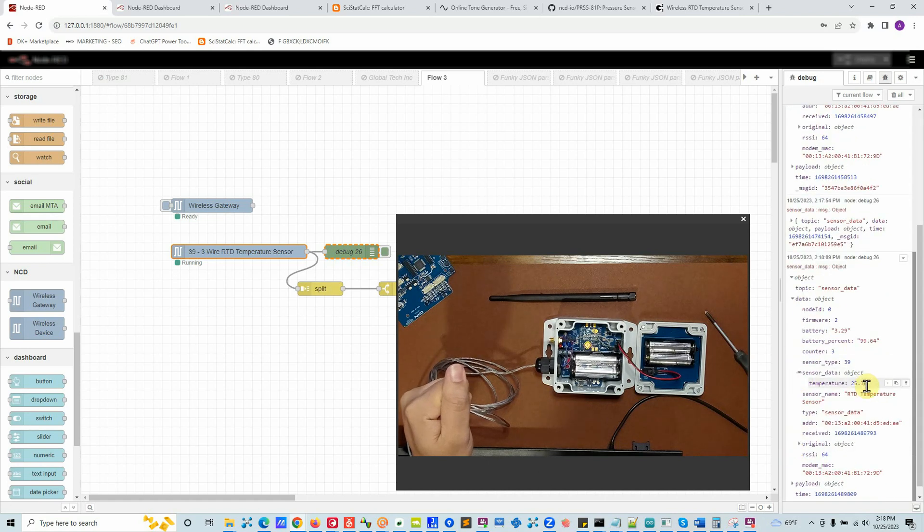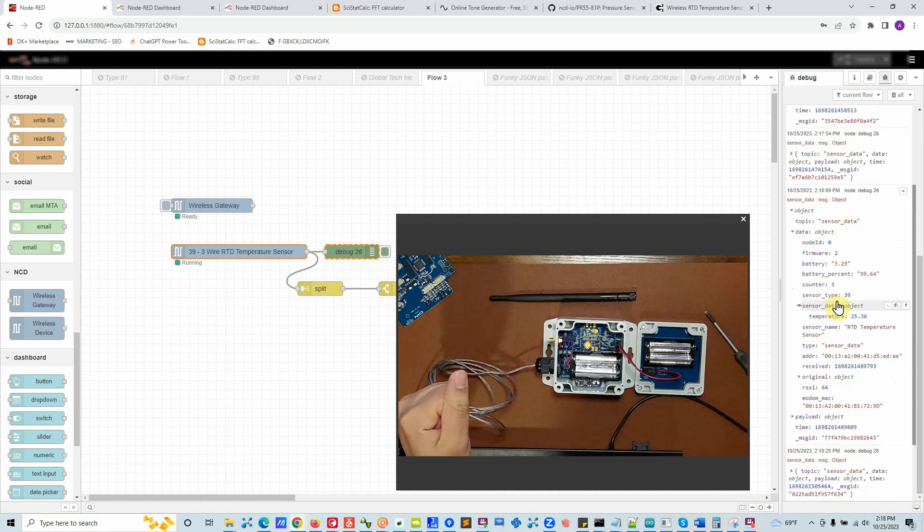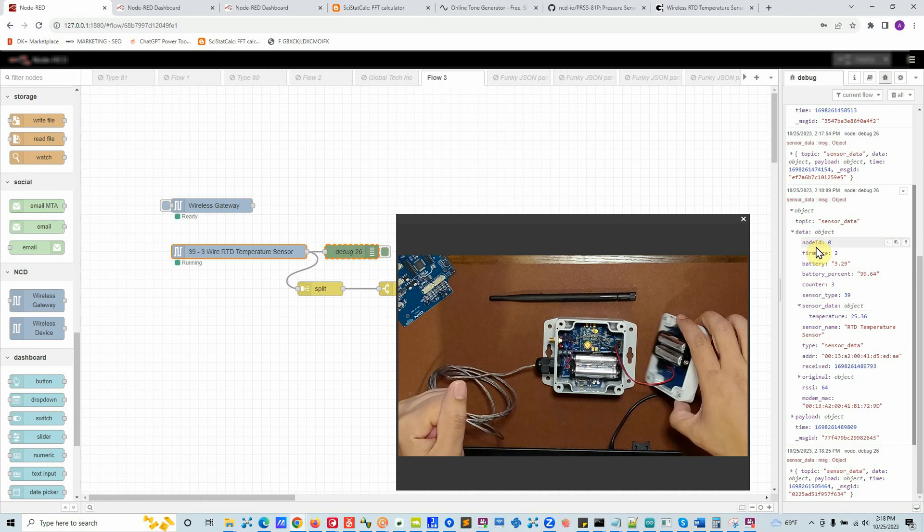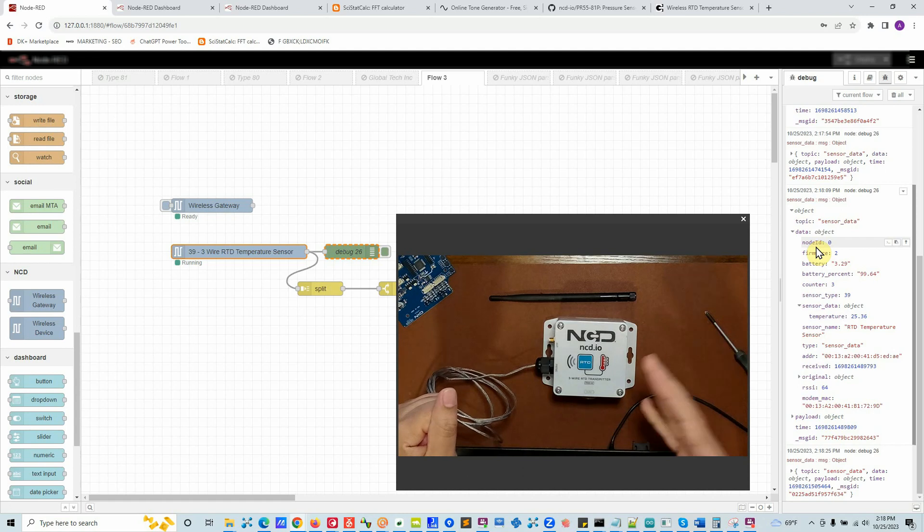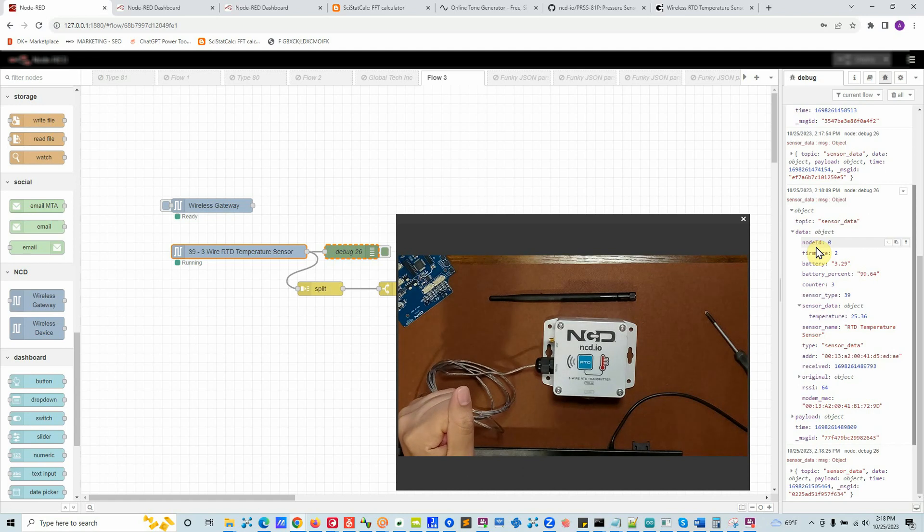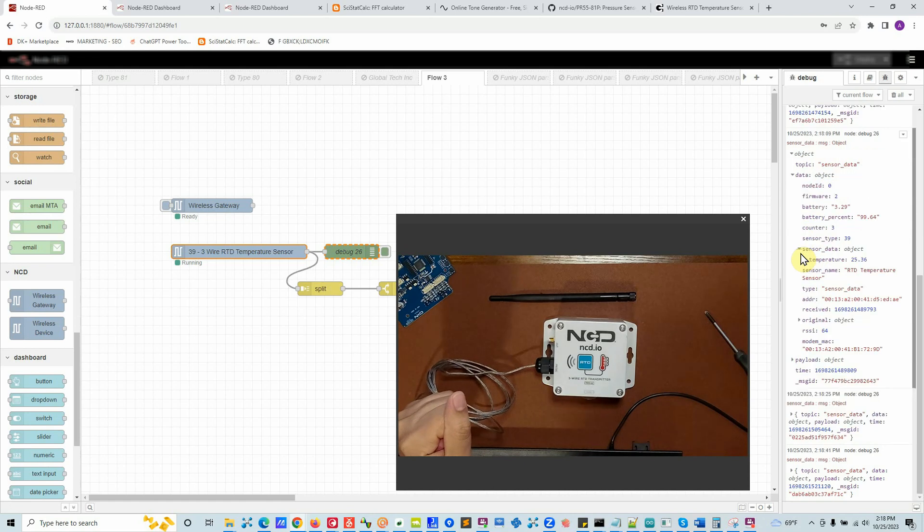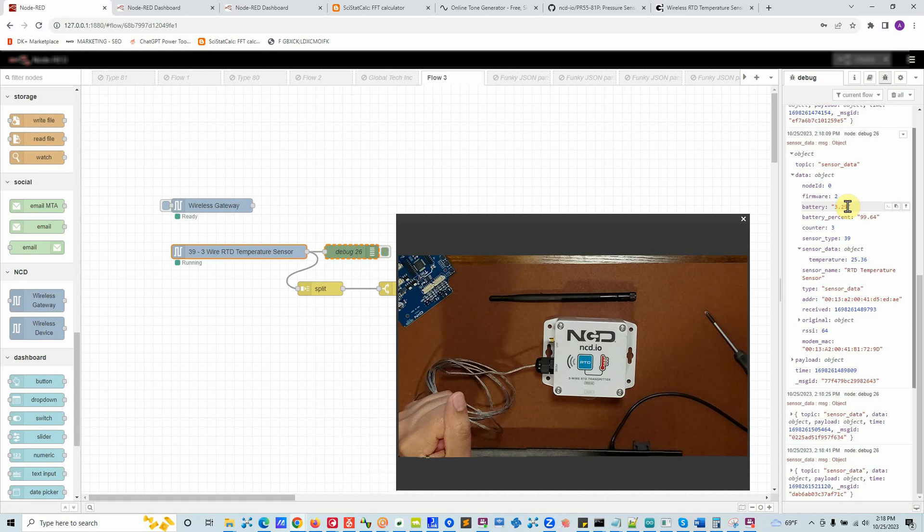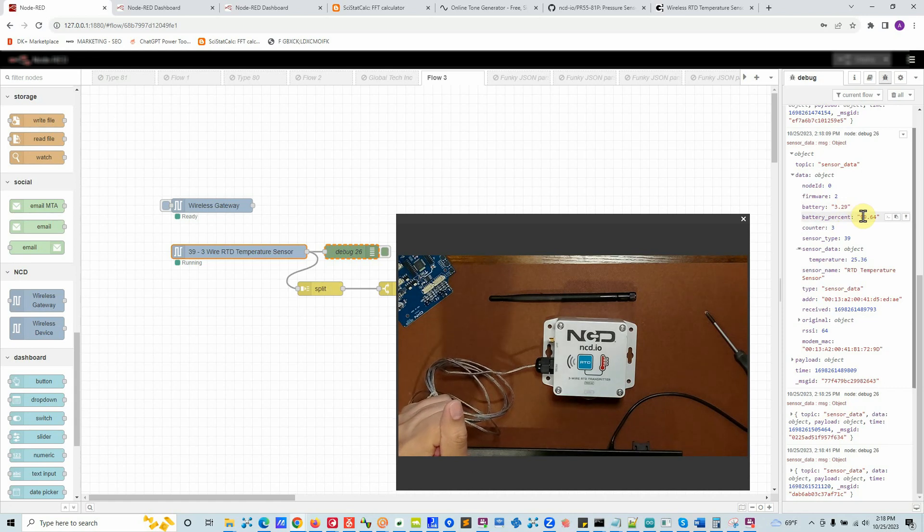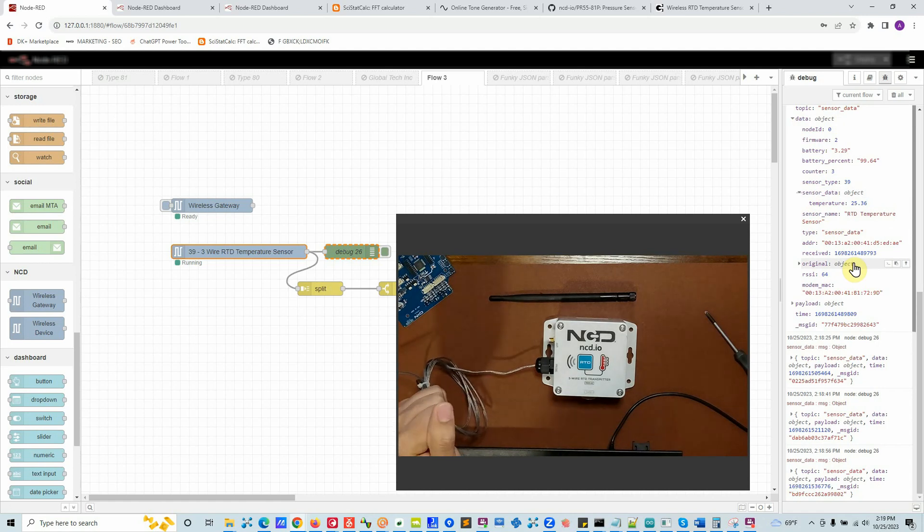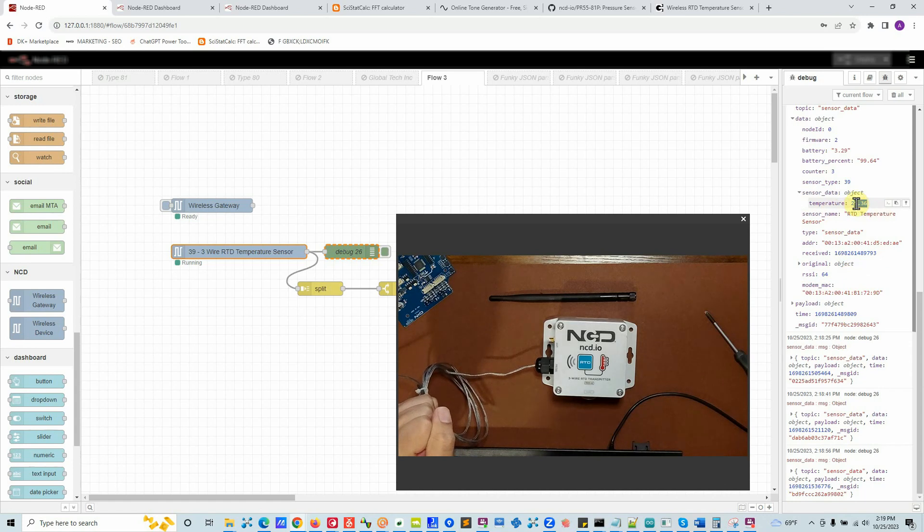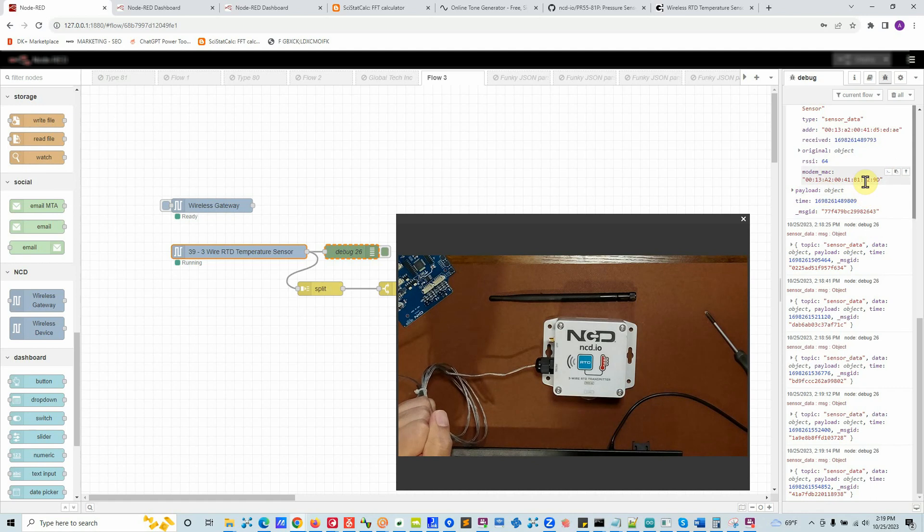The temperature starts to increase. Let's talk about all these parameters. Node ID is a user configurable parameter you can change. Sometimes folks give it a number and then put a sticker on the side of the box so they can see from a distance, or sometimes they use it just to mark what device it is. Then firmware version: each device comes with a firmware version. As we make changes, make improvements, we'll install new firmwares and you will see this number increase. Then the battery voltage: this is a new device and the battery voltage should be around 3.3 volts. The battery percentage converts this value into percentage. Then the counter: every time the device sends a message it increases the counter value. Then we got the data, and as I said we only have one data point which is temperature. Sensor name: RTD wireless temperature sensor. And then the MAC address of the sensor, this is unique - every single sensor has its own MAC address.